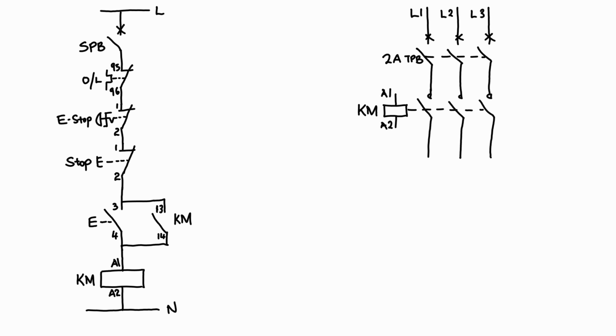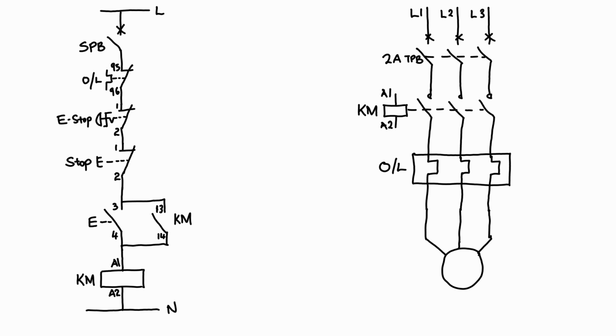What this means is that this is the same KM which is operating these contacts that are switching the main supply to our electric motor. It's also the same contactor which is switching on this 13 and 14 on the auxiliary contacts. So from the contactor, we go to our overload relay, and from our overload relay, we go to our electric motor, which is a three-phase motor. So this is basically it.